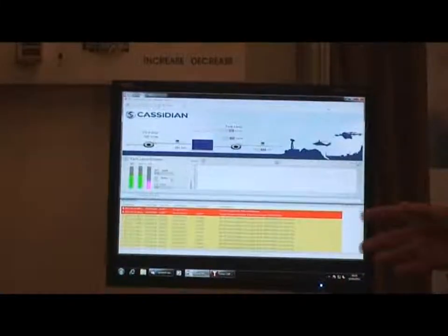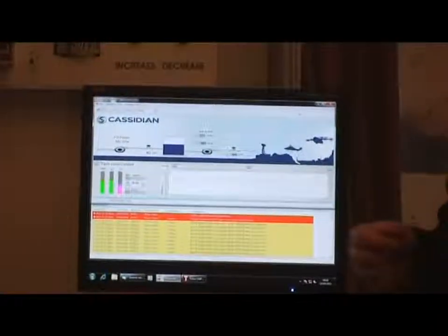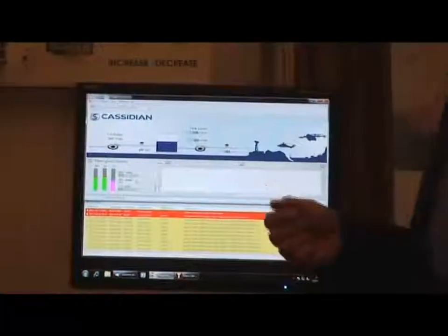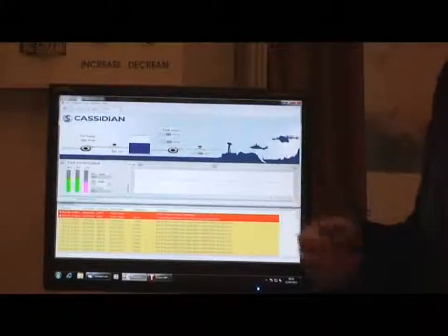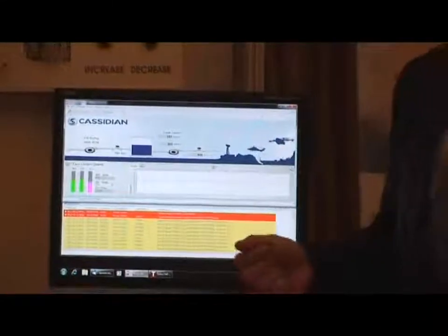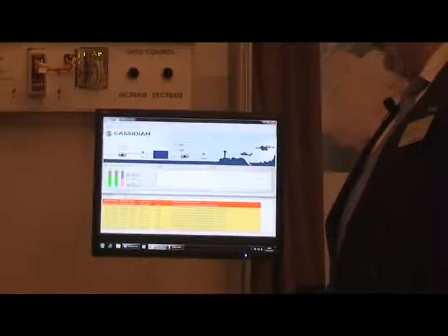Now that at the moment is a completely undefended system which can be attacked. Now there are different ways of attacking it. It could well be that someone, a service engineer out in the field, plugs a USB stick into a remote telemetry unit or a distributed control system, or it could be that you have some piece of malware which comes down from your corporate network through a connection, or some places they allow email in the control room, and what I've done here is simulated that. So we have an email which appears to come from Wago, people who manufacture the PLC, with an updated manual, but also some information on critical patches that need to be applied.